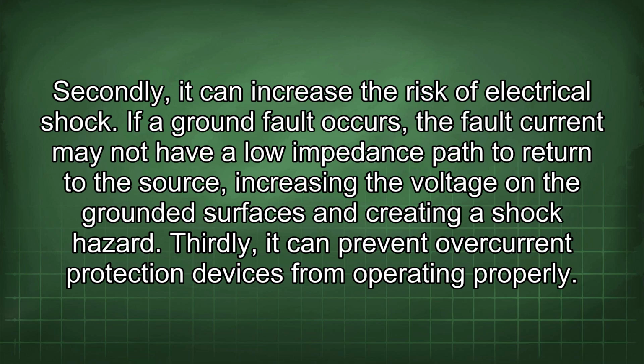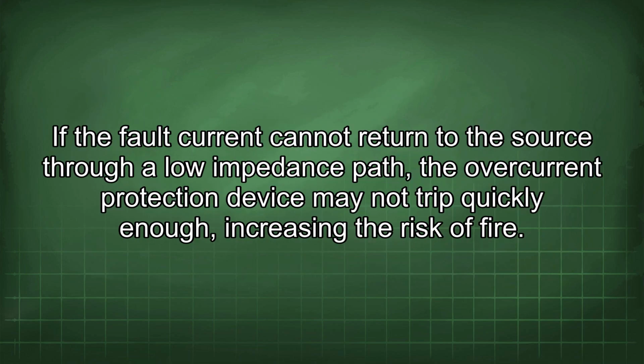If a ground fault occurs, the fault current may not have a low impedance path to return to the source, increasing the voltage on the grounded surfaces and creating a shock hazard. Thirdly, it can prevent overcurrent protection devices from operating properly. If the fault current cannot return to the source through a low impedance path, the overcurrent protection device may not trip quickly enough, increasing the risk of fire.